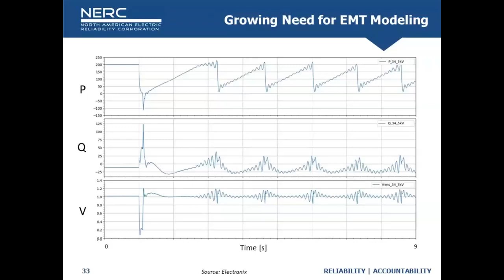active power starts to increase, the unit starts to experience some small signal instability and starts to oscillate, and the POI voltage and the terminal voltages start to oscillate as well. They hit a condition where voltage hits 1.2, which initiates ride-through mode again, and so the unit snaps back into a drop in active power output. Voltages again recover, the unit starts to recover back out of ride-through mode, small signal instability occurs again, and the process reiterates. So this is a good example of small signal instability, controls instability, control mode cycling, and none of this is picked up in the positive sequence simulation tools, the dynamics tools. It really requires some EMT modeling to be able to identify these types of things in some situations.